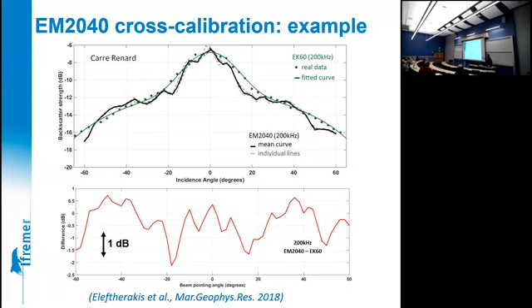So you see it's not perfect, but quite aligned on zero, meaning that the average measured levels given by the constructor were okay. And the fluctuations around this are in the plus minus 1.5. Okay, and this you have to do again and again and again because you want to do it for all the frequencies of the multi-beam, if it is a multi-frequency one, and all the various modes, shallow, deep, and so on. That's it. So we are in the middle of it. We are fairly advanced for the frequency range corresponding to the 2040, meaning 200, 300, 400 kilohertz.